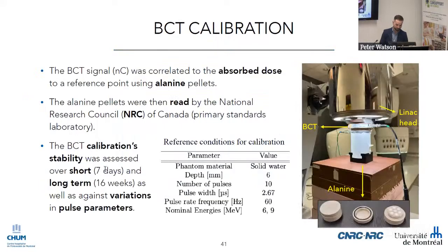So that's some work we've done in collaboration with colleagues from the NRC in Ottawa. They provided us with alanine pellets, which are reference dosimeters that can be traced to primary standards of absolute dose to water. And they're really the reference for FLASH regimen. They're dose rate independent, so you can get a clinical accuracy of dose below 1% with alanine. So they shipped us the alanine by mail, and we calibrated our BCT.